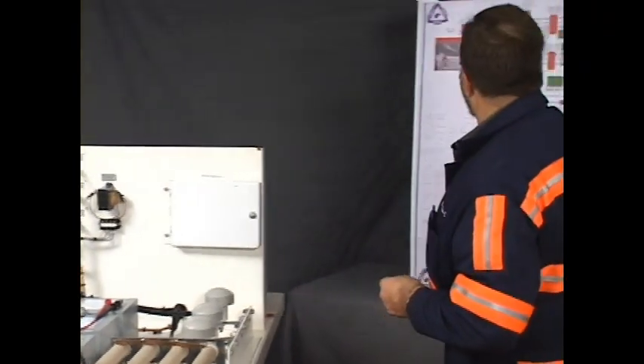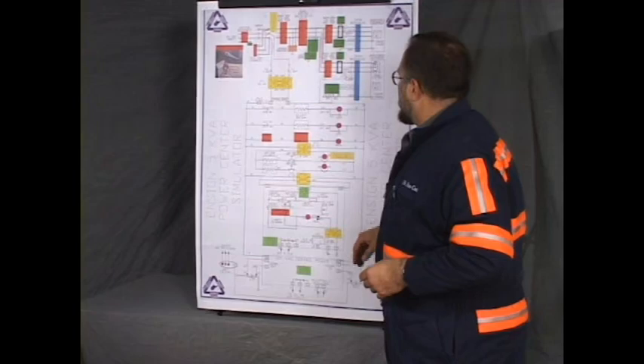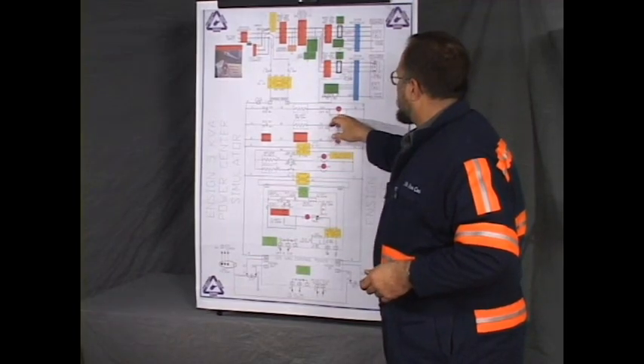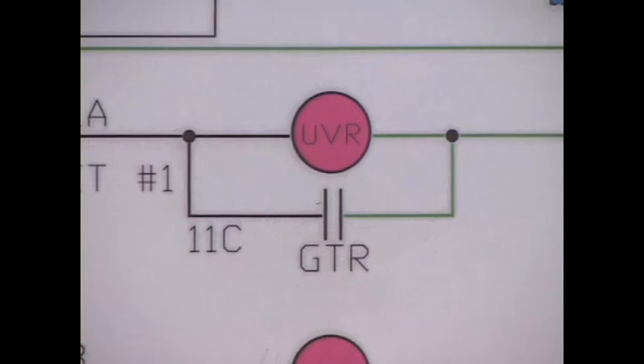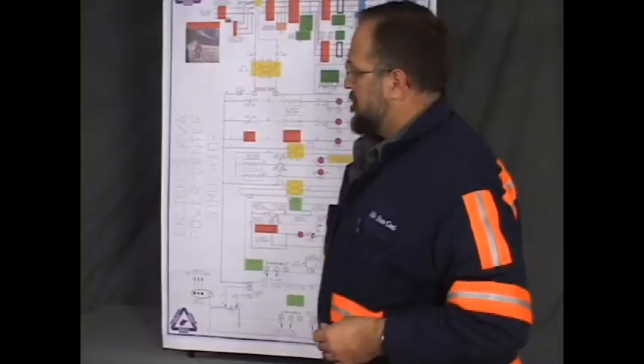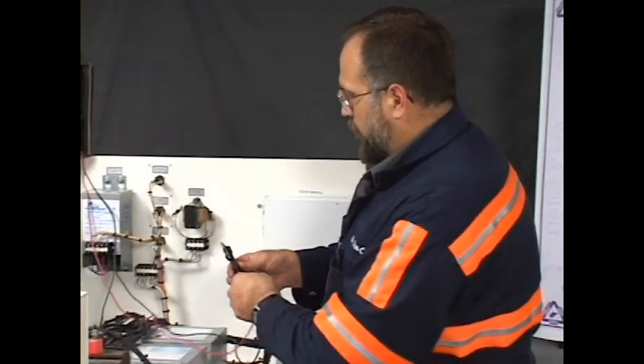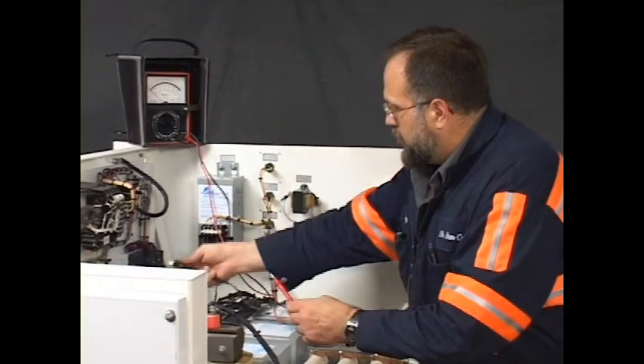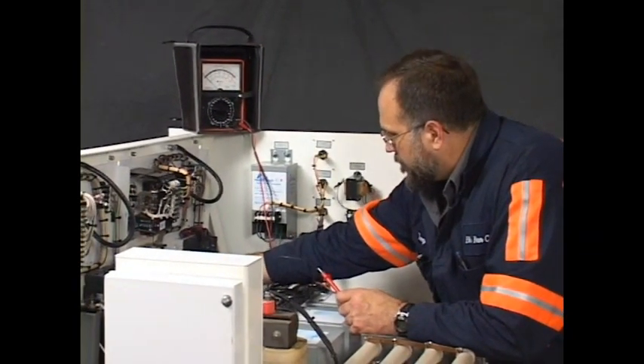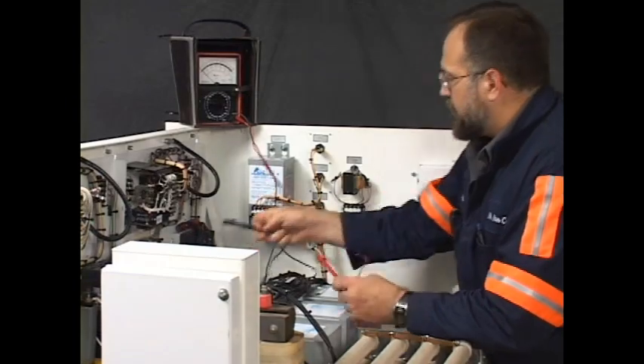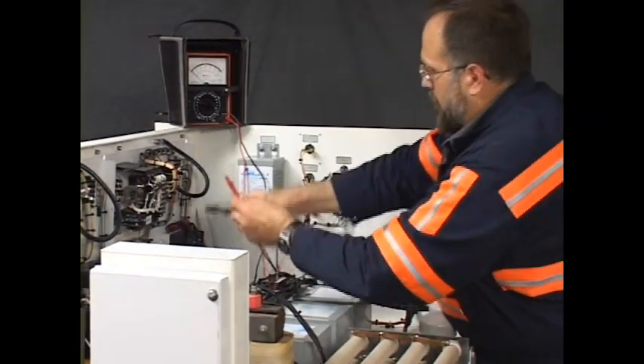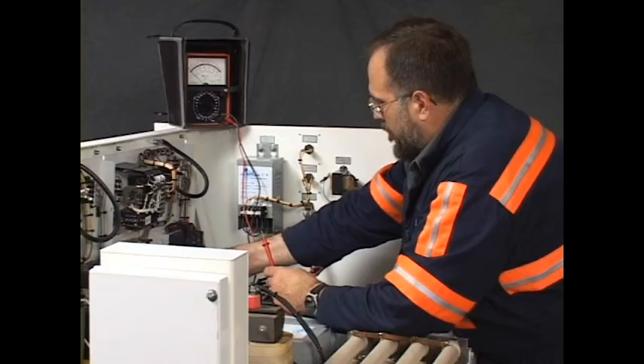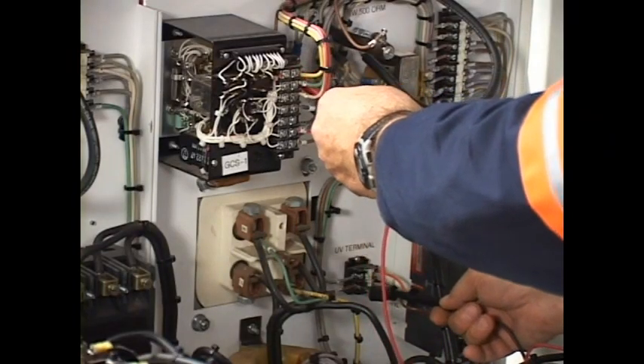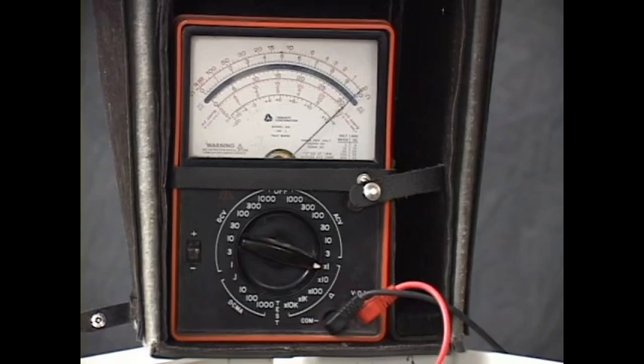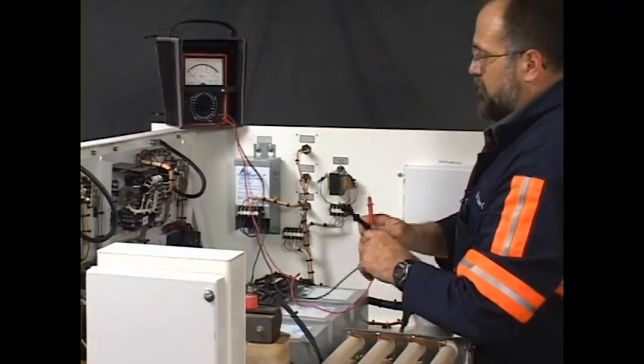Now, the part of the circuit that we're concerned with is this GTR. So let's read it and its wires associated with it first. Okay, I'm going to read the circuit that connects it to the UVR circuit on 11C. And we have a terminal block here for the UV. The UV is actually part of the circuit breaker. It's internal to the breaker, and it's not readily accessible for reading, but its leg wires are. I'm going to put one probe on 11A, and I'm going to read to 11C on top. And there you have it. I have a circuit. That's as it should be.